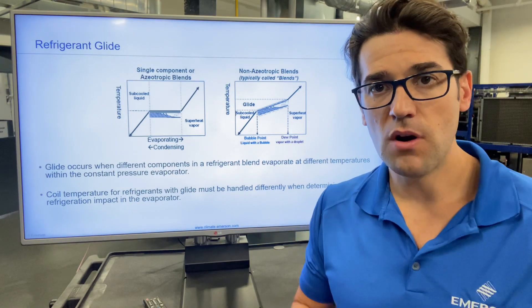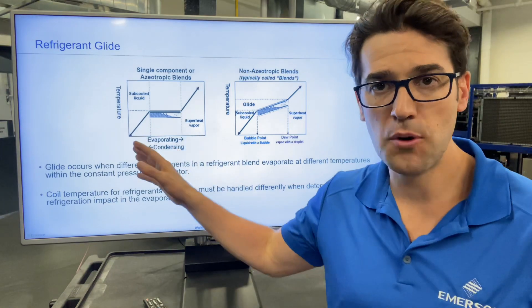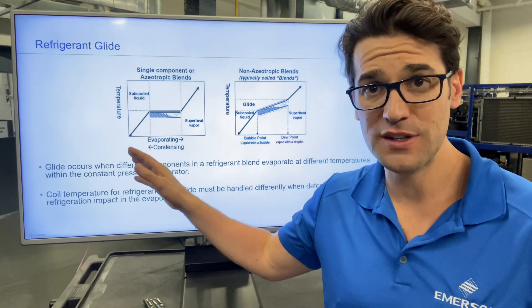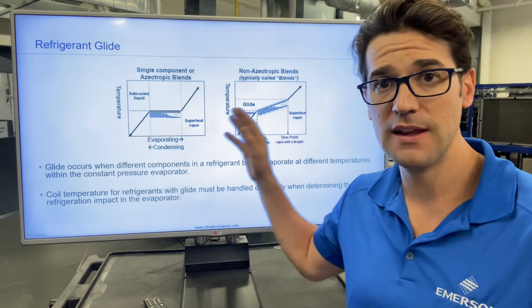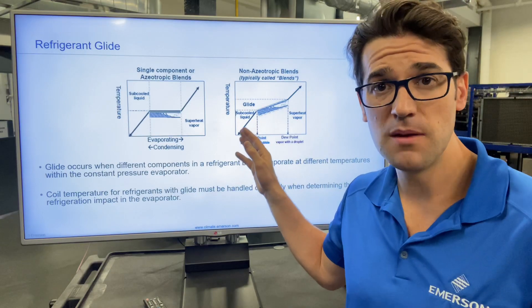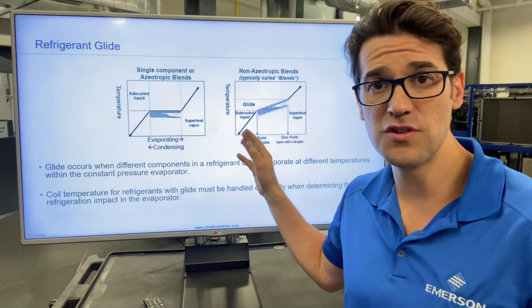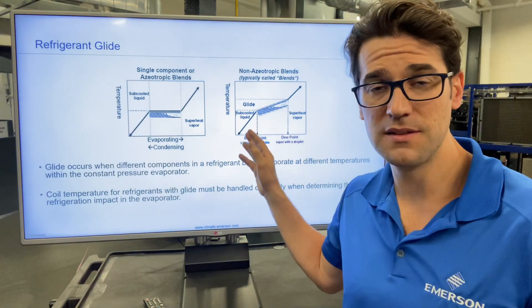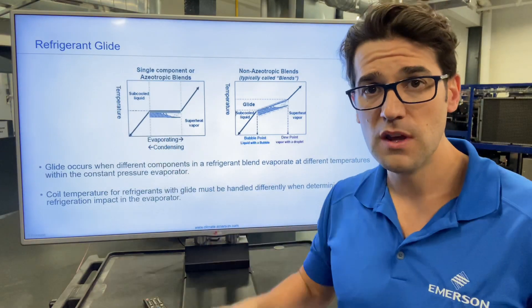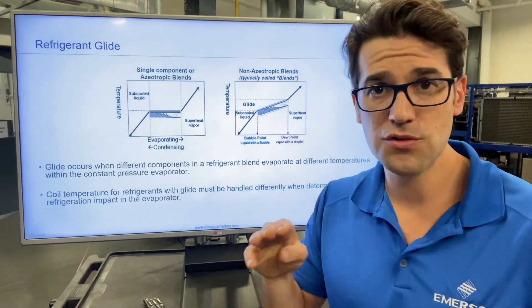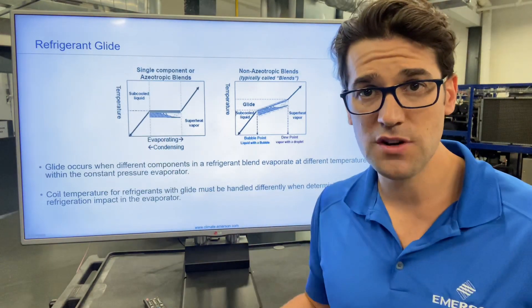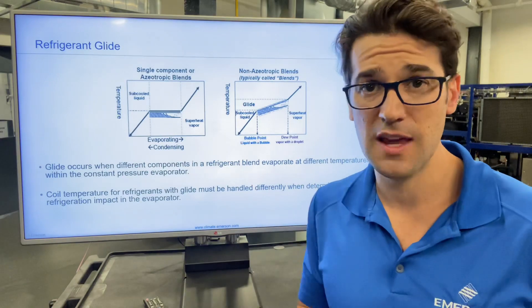I got a chart behind me here. I have a single component refrigerant like R22 and then a non-azeotropic, which is multiple refrigerant blends. With R22, when you're going through your evaporator or condenser at a constant pressure, you're going to have a constant temperature.